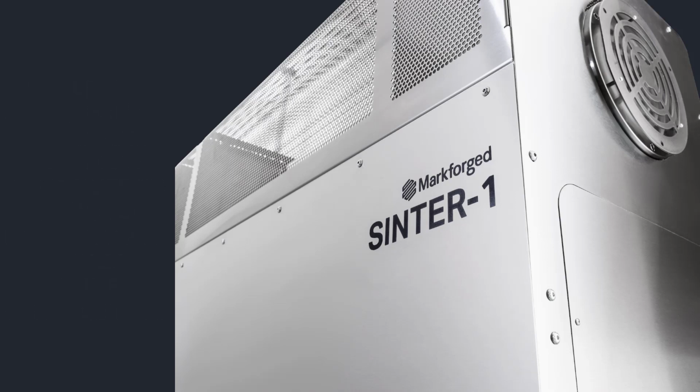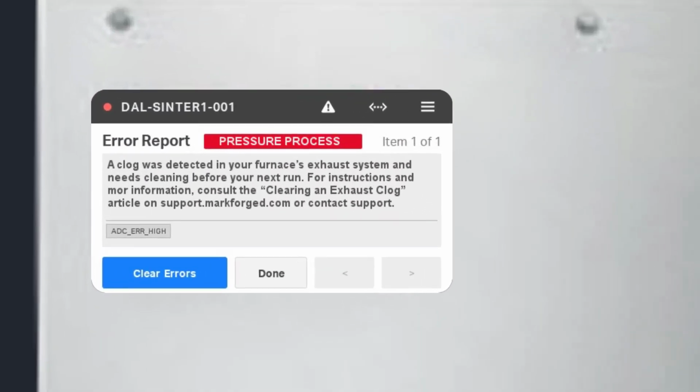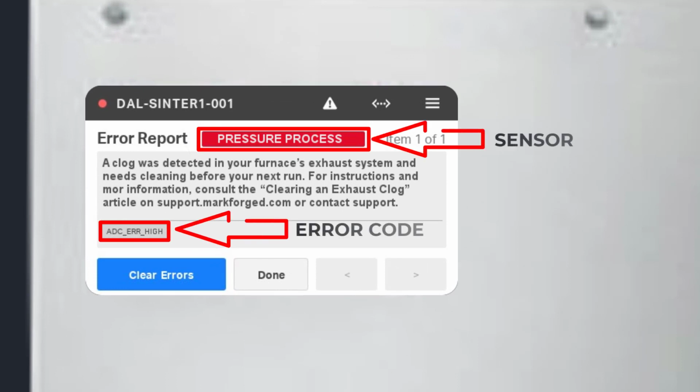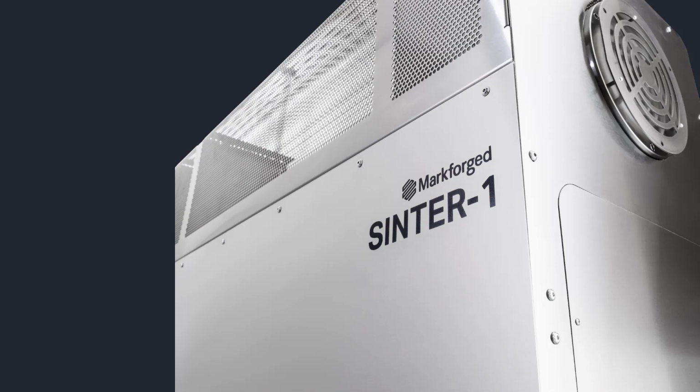Each error code is issued from a specific sensor, but a given code may have many possible causes. For example, an ADC error high code may be caused by a wide range of issues, not just a clog in a specific location. Markforged support uses machine logs and telemetry data to perform differential diagnosis of machine errors.